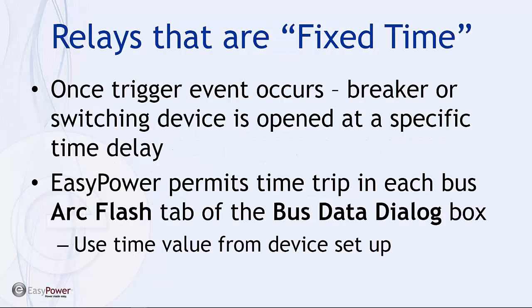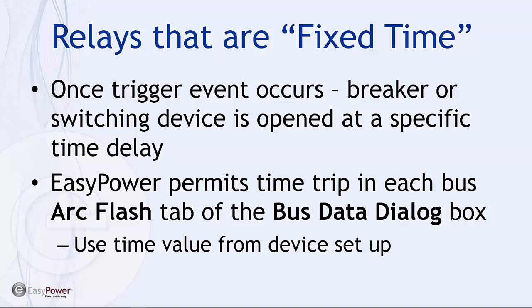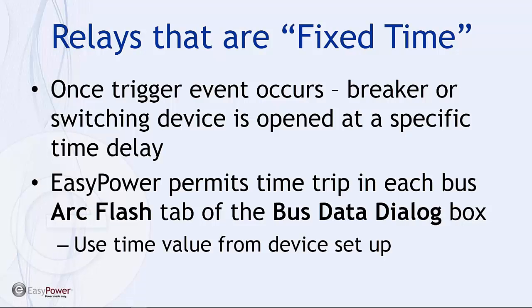The relays that I consider to be fixed time are defined as such because once the trigger event occurs, the breaker or the switching device is opened at a specific time delay, which is a function of the circuit element, the device that we're utilizing for the trip settings, independent of how long the trigger event has lasted. In terms of an arc flash sensor, an arc flash sensing relay, once that trigger has happened, once the arc has been determined or detected, then there is a fixed time delay before the breaker opens.